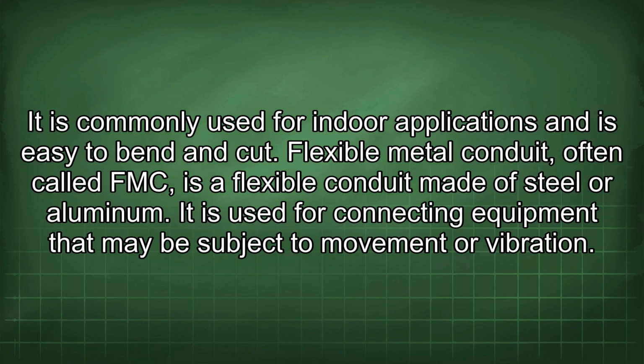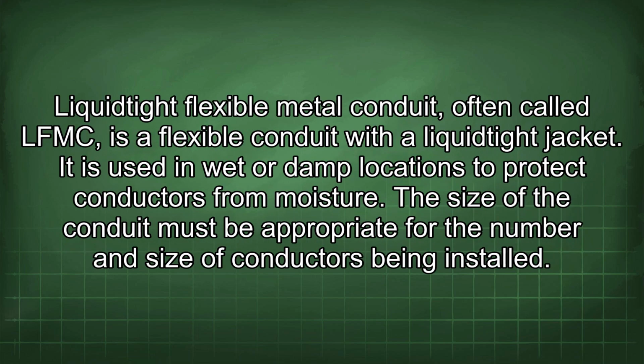Flexible metal conduit, often called FMC, is a flexible conduit made of steel or aluminum. It is used for connecting equipment that may be subject to movement or vibration. Liquidtight flexible metal conduit, often called LFMC, is a flexible conduit with a liquidtight jacket. It is used in wet or damp locations to protect conductors from moisture.